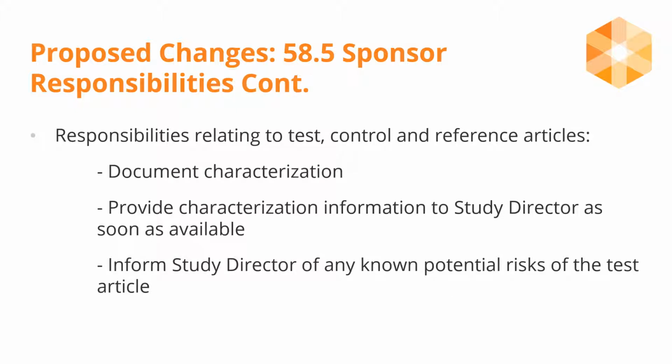The proposed changes also address sponsor responsibilities for test, control, and reference articles. Sponsors need to document and provide characterization information to the study director as soon as possible. Also, the study director needs to be informed of any known potential risks of the test article.